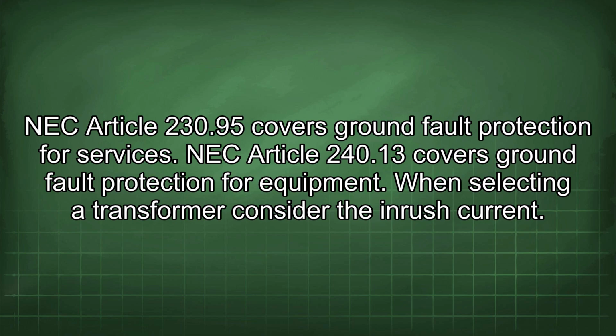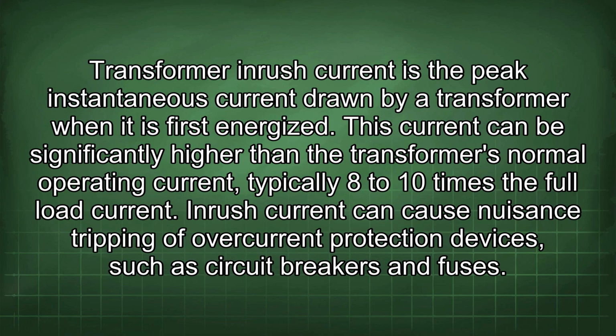When selecting a transformer, consider the inrush current. Transformer inrush current is the peak instantaneous current drawn by a transformer when it is first energized. This current can be significantly higher than the transformer's normal operating current, typically 8 to 10 times the full load current. Inrush current can cause nuisance tripping of overcurrent protection devices such as circuit breakers and fuses.